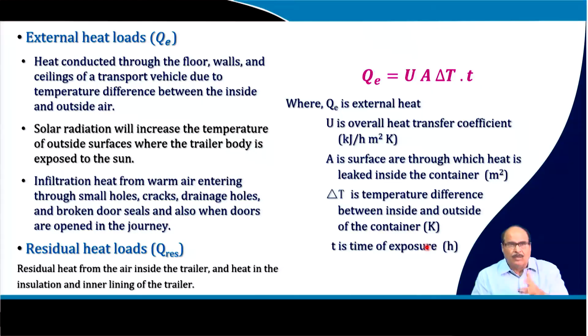So, the external heat load Qe is equal to U A delta T multiplied by small t. Qe is the external heat, U is the overall heat transfer coefficient, A is the surface area through which heat leaks inside the container, delta T is the temperature difference between inside and outside of the container, and small t is the time of exposure. Using these known values, one can calculate the external heat. Now, you have calculated the internal heat load and external heat load, and you know the residual heat load. So, one can calculate the total cooling capacity.